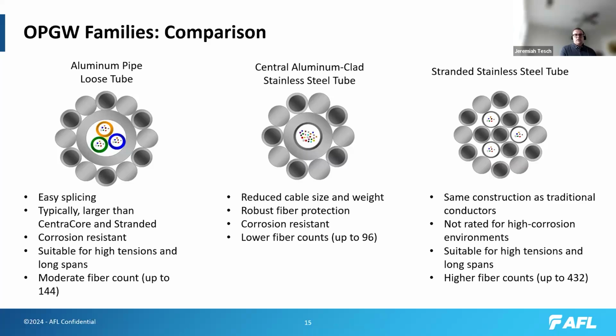This also, like I said, offers your corrosion resistance and crush protection with that aluminum pipe. And then this also has the lowest fiber count potential as you're just using one stainless steel tube. But a lot of people, when they replace the traditional shield wire, maybe they have a 3/8 inch shield wire, so they want to use the smallest potential OPGW to replace it. We often use this style here because it has the smallest potential diameter. All right, and then the third style is stranded.